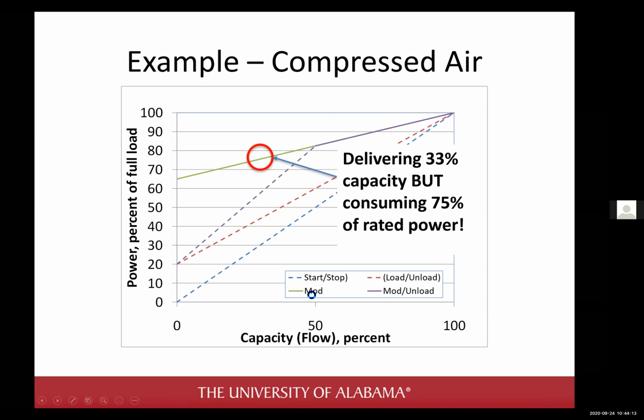And so the modulating control, unfortunately, uses a lot of power still, even if you have a low amount of air being used, because there's a big pressure drop across this butterfly valve. And so, in summary, the amount of power they were using was 75%, so 75 horsepower. They were still using 75 horsepower of 100 horsepower to deliver 33% of the capacity. There's a bunch of other lines in here, but really we're just concerned with this green line, because that's the way this specific compressor was controlled.